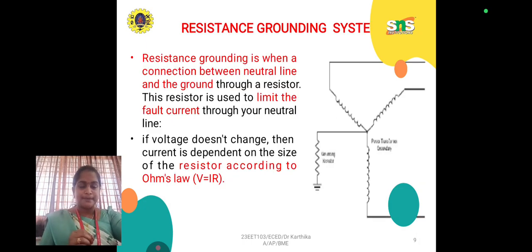Resistance grounded system. Resistance grounding is when a connection between the neutral line and the ground is made through a resistor. Here, this resistor is used to limit the fault current through your neutral line. See, if voltage doesn't change, then the current is dependent on the size of the resistor according to our Ohm's law. Ohm's law is V equal to IR. See the diagram. Here we are using resistance before the grounding connection.